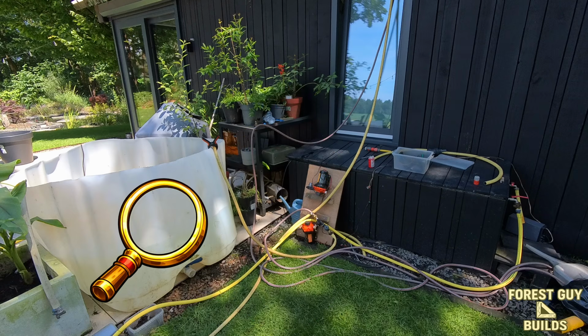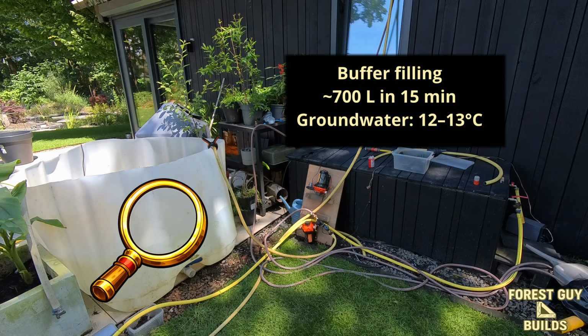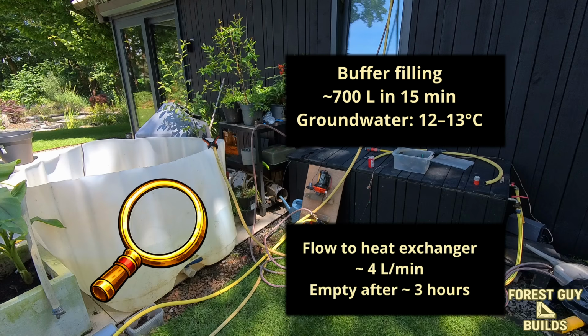That means some of the cold energy is already being lost before the water even reaches the heat exchanger. For a temporary test setup that's acceptable, but it's something to improve in the next phase. Right now I'm using this reservoir as a cold buffer. I'll fill it up in about 15 minutes with roughly 700 liters of cold groundwater, and then the small pump slowly extracts the cold energy at a flow rate of about 4 liters per minute. At that rate the system can run for almost 3 hours before the entire content of the reservoir has passed through the heat exchanger.